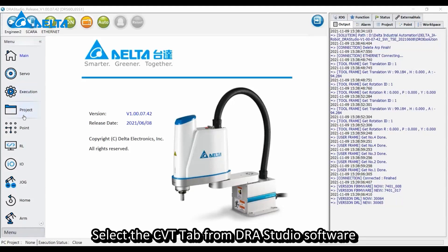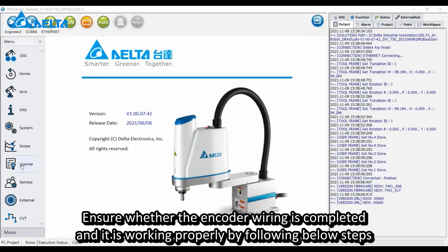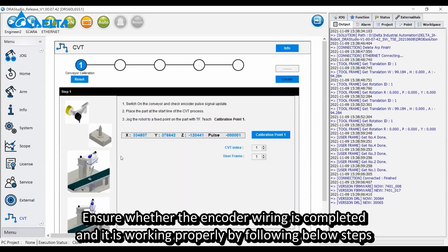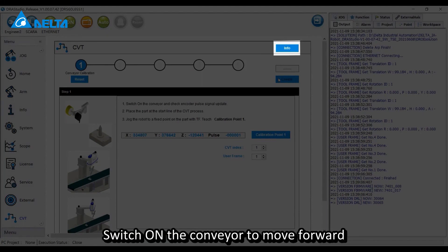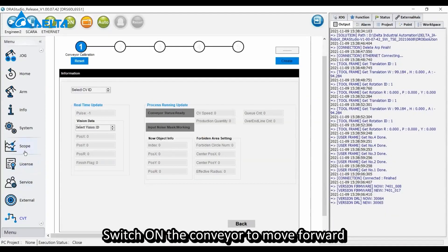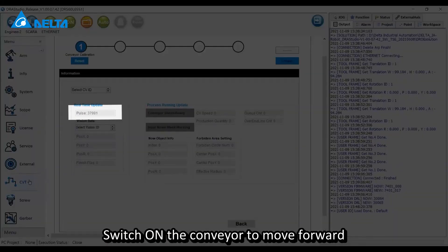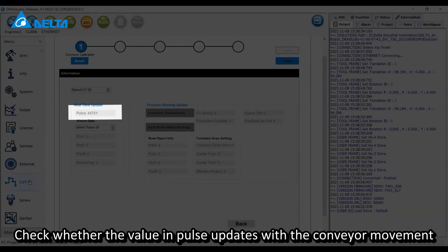Select the CVT tab from DRA Studio software. Ensure the encoder wiring is completed and working properly by following these steps. Click Info, switch on the conveyor to move forward, and check whether the value in pulse updates with the conveyor movement.